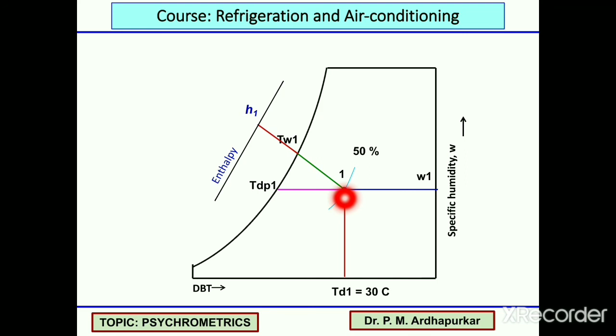Similarly, you can find out the wet bulb temperature corresponding to point 1. Here on this saturation curve, the temperature scale is also provided. So that will give you the wet bulb temperature of the given air at point 1. For enthalpy, further extend this constant wet bulb temperature line to the enthalpy scale and read the enthalpy value there. In order to get the dew point temperature of the air which is at 30 degrees centigrade dry bulb temperature, go horizontally here and there you can read the temperature. That will be the value of dew point temperature for this air at point 1.